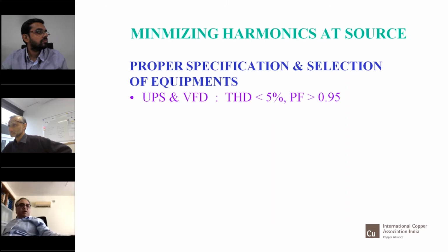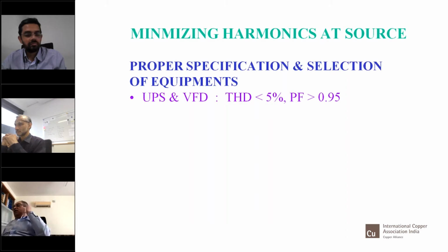This slide was prepared by me about 5-6 years ago, and I've been using it. Today I have changed this, especially as I work for large data centers, so it is very important for me. There I have changed the specifications to THD less than 3% and power factor higher than 0.99. We have made it so stringent that we don't buy any UPS which does not conform to these standards, because you buy a UPS to take care of the IT equipment, but if it introduces such large harmonics in the systems, we have another problem on hand.